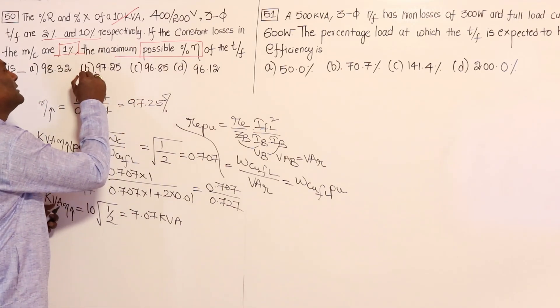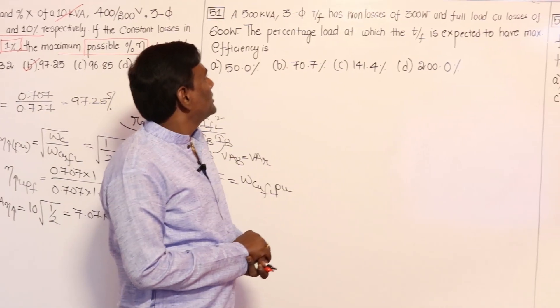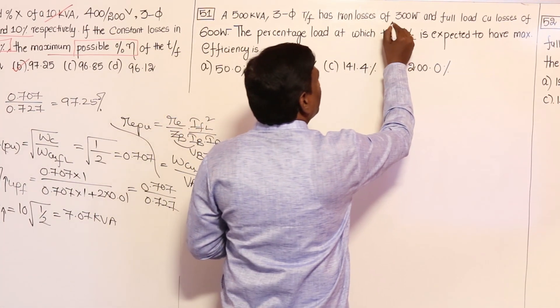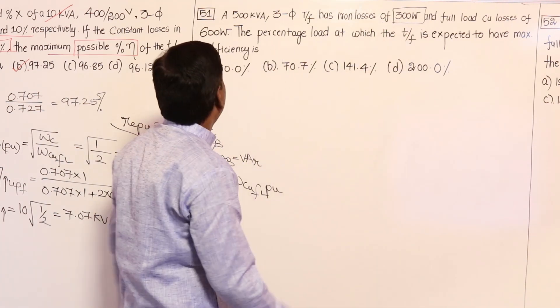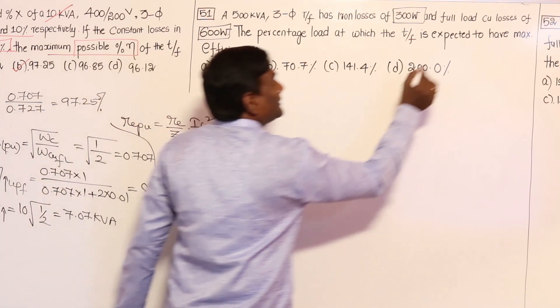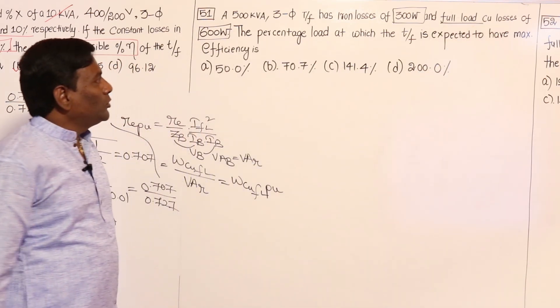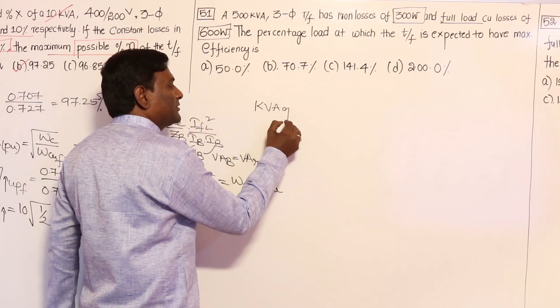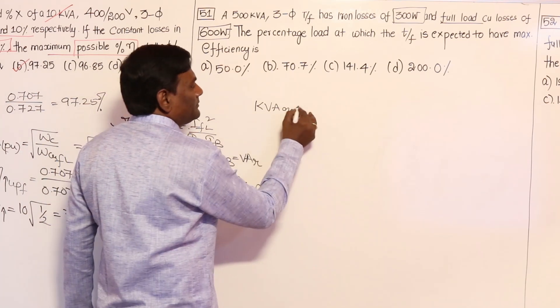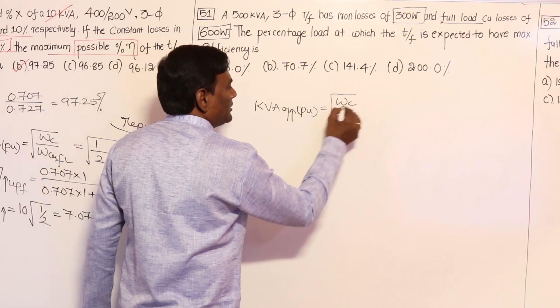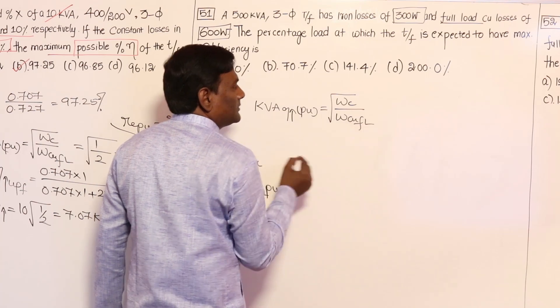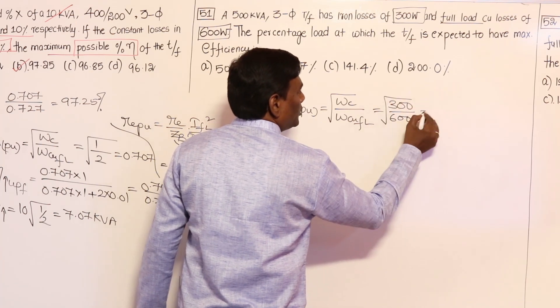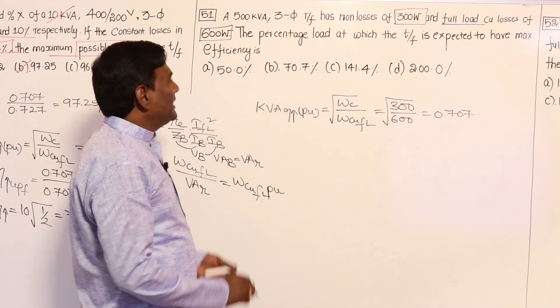Now let us take one more question. A 500 KVA three-phase transformer has an iron loss of 300 watts and a full load copper loss of 600 watts. We need to find the percentage of load at which maximum efficiency is expected. KVA at maximum efficiency in per unit equals the square root of core loss divided by full load copper loss, which is the square root of 300 divided by 600, giving 0.707 — so maximum efficiency occurs at 70.7 percent of rated KVA.